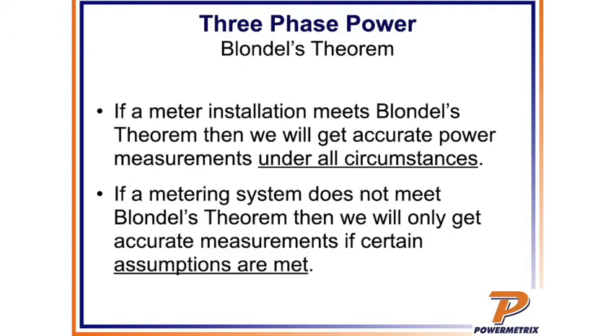Back in the days when the electromechanical meters were around, engineers were trying to find a way to reduce cost. We'll talk about the Z-coil. That's a little bit unique where they actually removed the PT to save costs there. But in most cases on the meters, it was pretty expensive to have a three element meter. So engineers tried to figure out, well, if I had two elements, and then I just did a little bit of a rewiring in the meter itself, maybe I could sum these two together and I could save a little bit of money on a meter. That was their whole reason why they came up with this violation of Blondel's theorem.